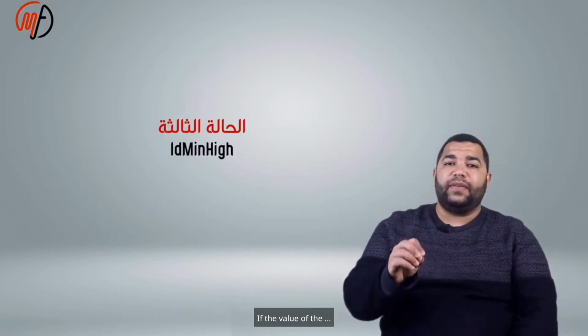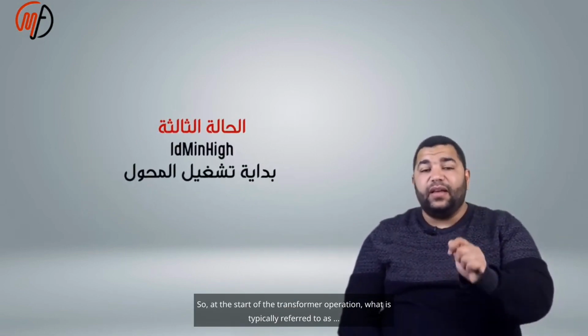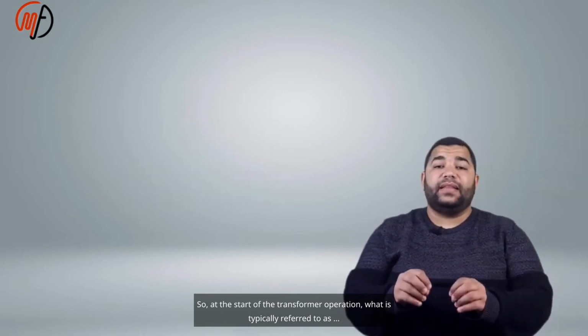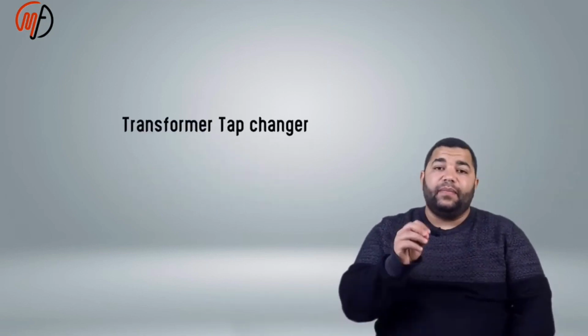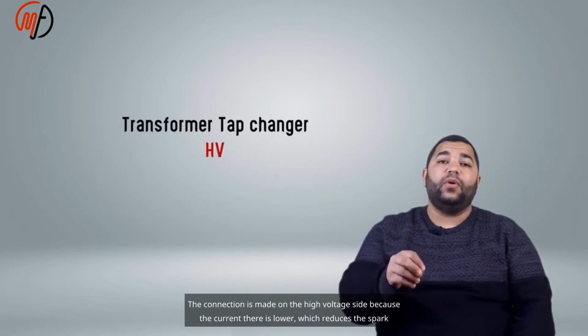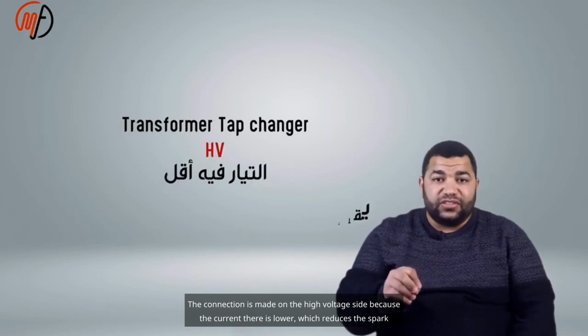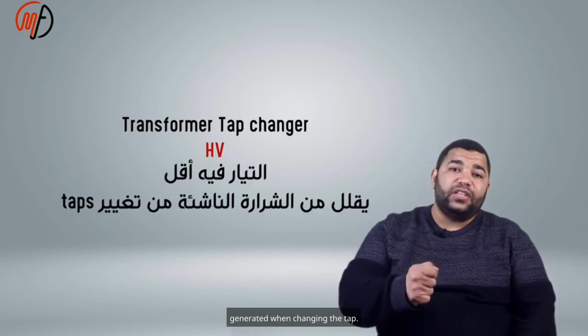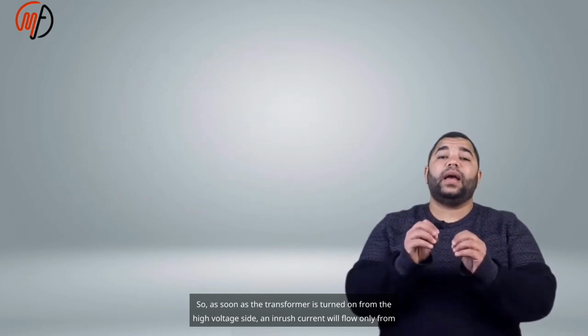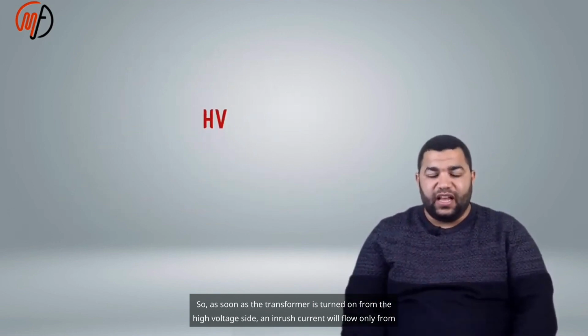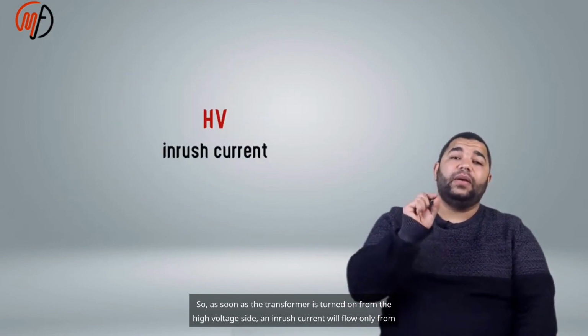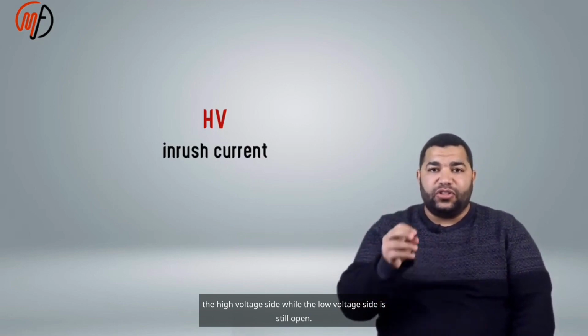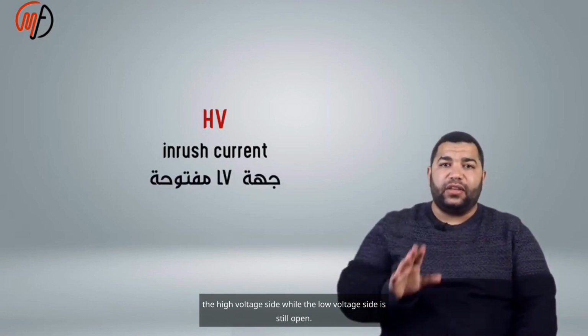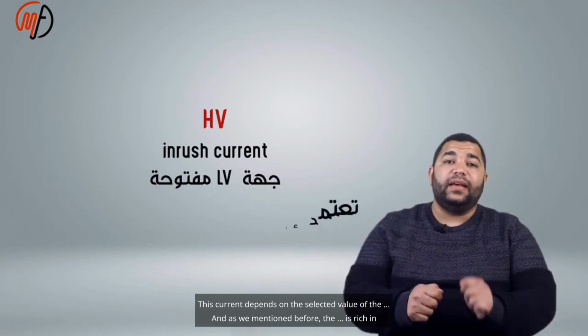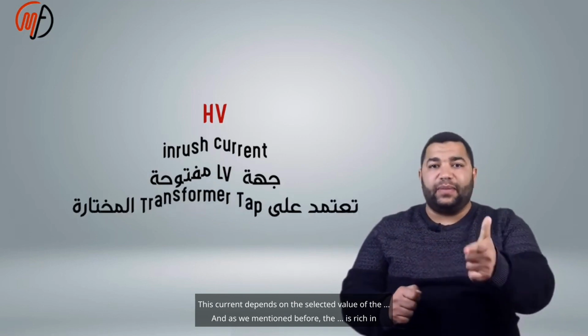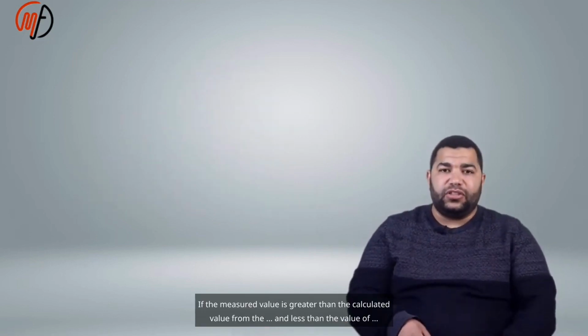So at the start of the transformer operation, what is typically referred to as the connection is made on the high voltage side because the current there is lower, which reduces the spark generated when changing the tap. So as soon as the transformer is turned on from the high voltage side, an inrush current will flow only from the high voltage side while the low voltage side is still open. This current depends on the selected value of the, and as we mentioned before, the inrush current is rich in harmonics.